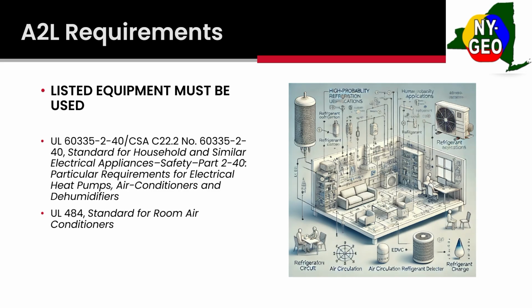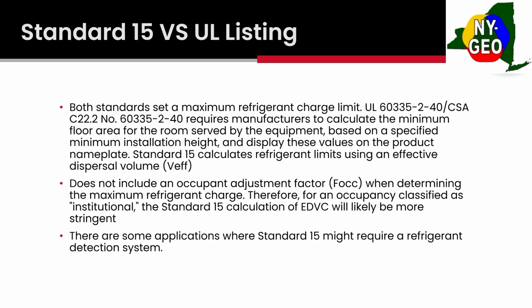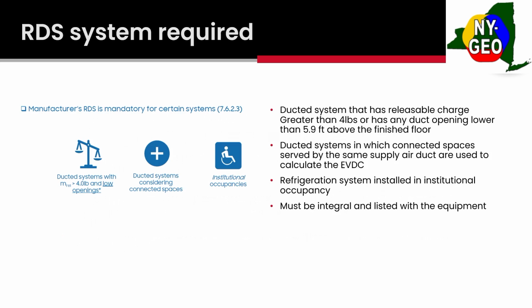ASHRAE 15 also has different standards for the refrigerant detection systems, the RDS, where UL does not explicitly require one. So that's a big difference right there. You need to know your charge and if you need an RDS system or not. And then lastly, the way that the manufacturers calculate their releasable charge is they use a set square footage and set ceiling height, whereas ASHRAE 15 is based on the room and your occupancy classification.